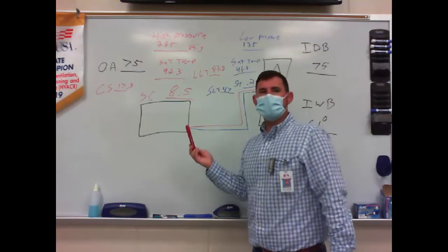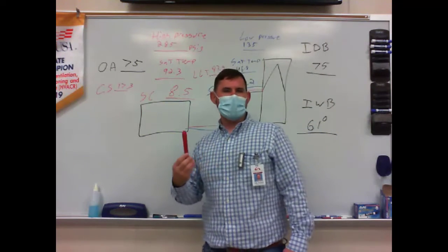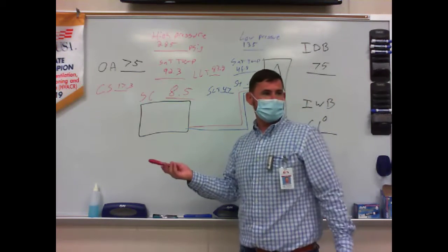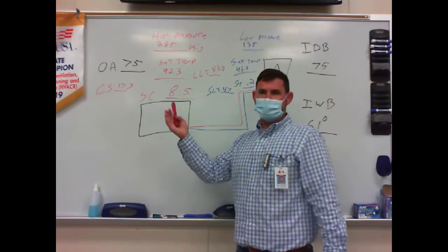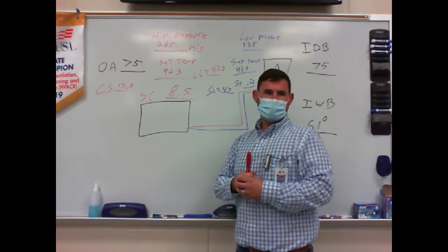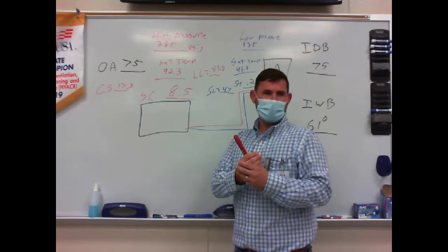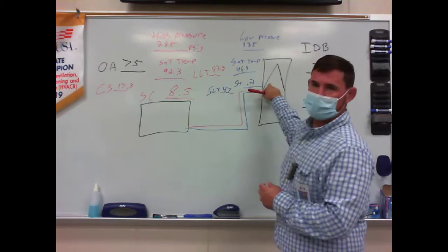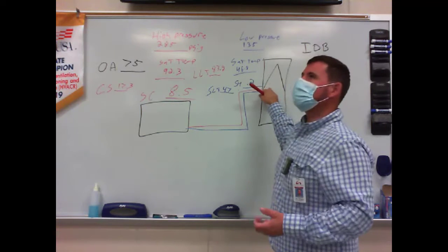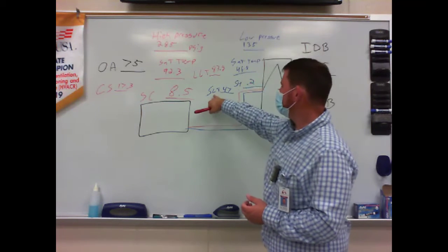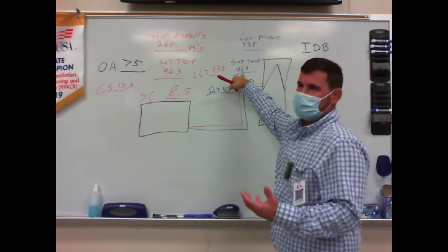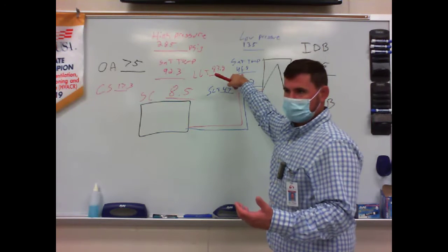So this one's a little tricky. If it were me, I would think I need to go in there and look at my sensing bulb on there. It may not be insulated, or it may not even be attached. So it may be sensing a lot of air temperature, letting that evaporator operate wide open, instead of sensing that cold line and trying to shut off and restrict it some more. Does that make sense? Will that make it ice up too? It wouldn't make it ice up because I'm saturating at 46 degrees, almost 47 degrees. So I'm not going to freeze anything at 47 degrees.